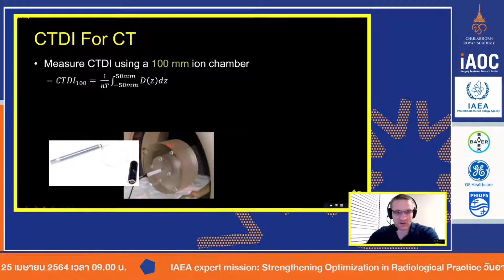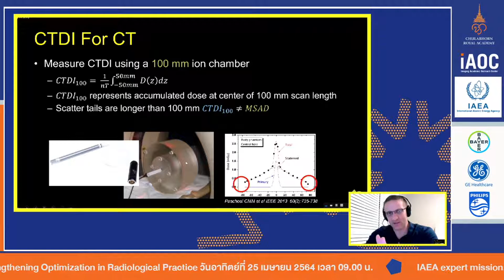And the point of this is the phantom, as I said, creates scatter. So this blue line down here would be if there was a very, very narrow beam going in. And so there's very little scatter created. So you have very little scatter tails. In our more modern CT scanners, they're 64 slice, 4 centimeters, or even the new 16 centimeter, or 320 slice scanners. These have very long tails. And there's a couple of things. We want to collect this because we want the ion chamber to measure all of this. But as you can see, even these ion chambers can't collect all of the scatter for 2 reasons. One, they're only 100 millimeters long. And 2, the phantoms are only 15 centimeters or 150 millimeters wide. So if you have a 16 centimeter, 160 millimeter wide radiation beam from a CT scanner, this phantom is actually not even as big as the beam itself. So the fact that we use CTDI, these phantoms and all this for CT itself, it's difficult to make the measurement.